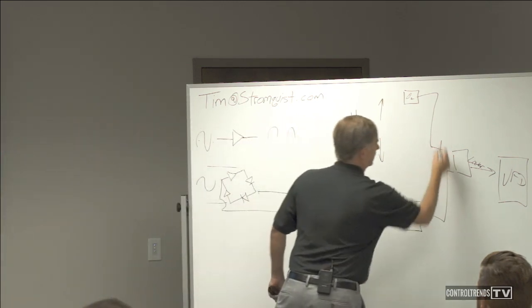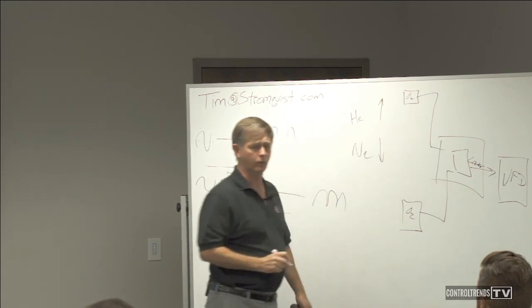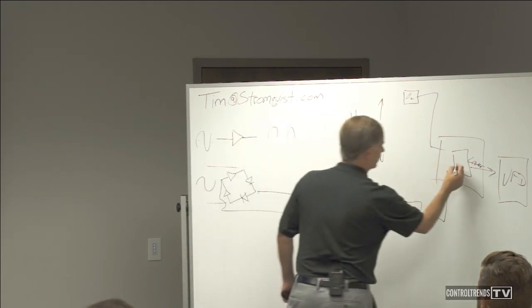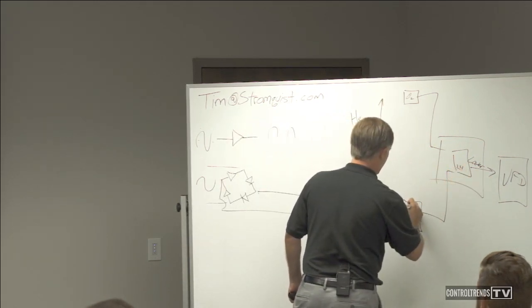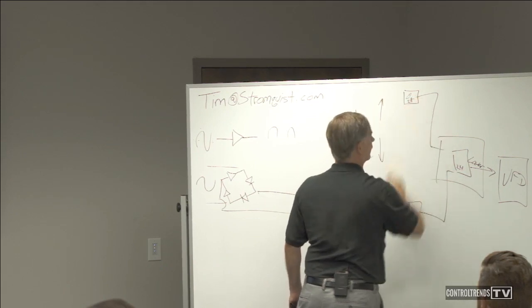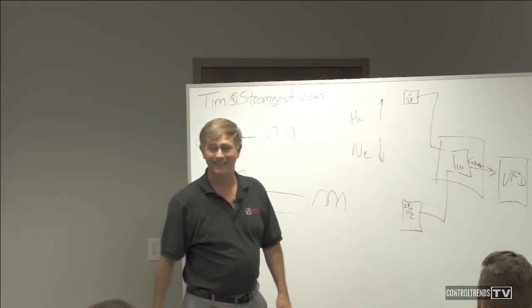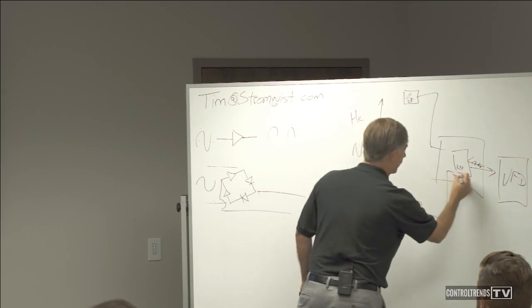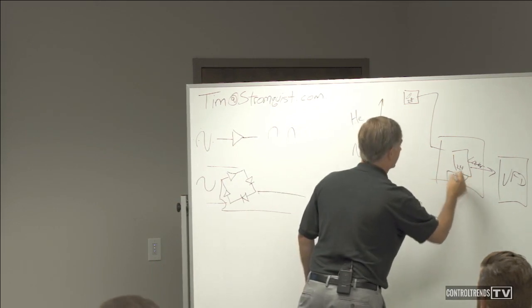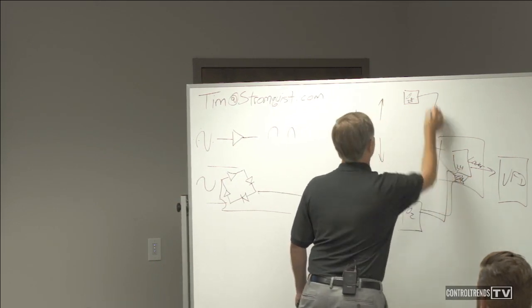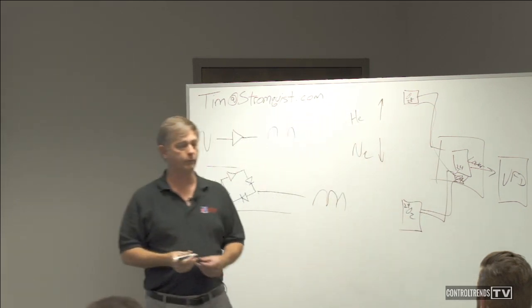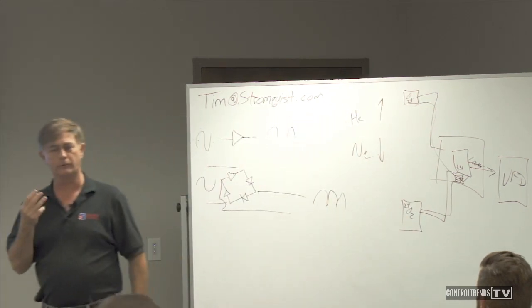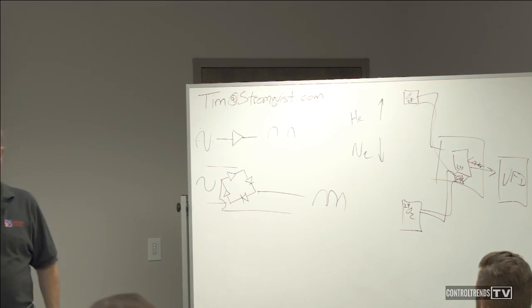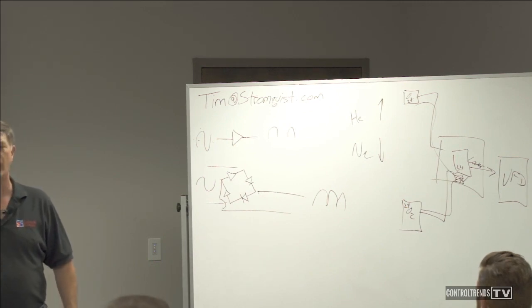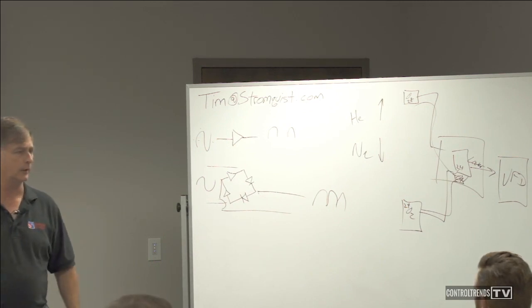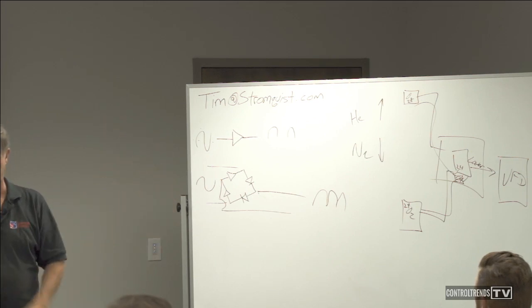So we've got this controller in a control box. This is 24 volts, this is 24 volts, this is 24 volts - all 24 volts AC, right? So we pop a transformer in here, 24 volts, and we power all three boards, because all three boards don't consume a whole lot of electricity, and that one transformer had plenty of power to do all three of these boards.